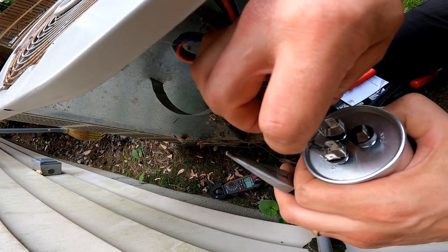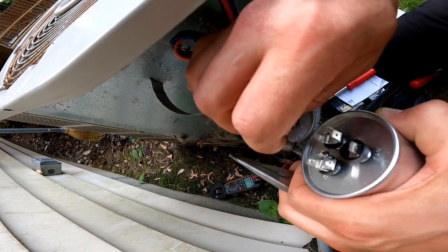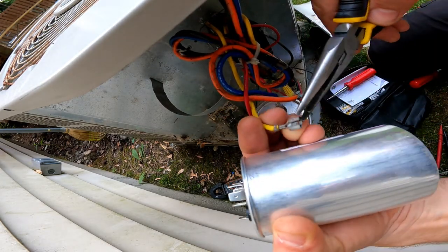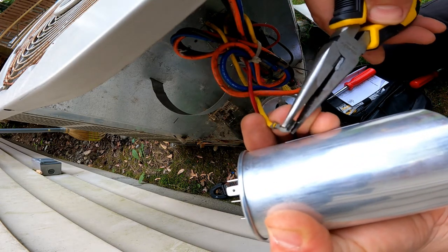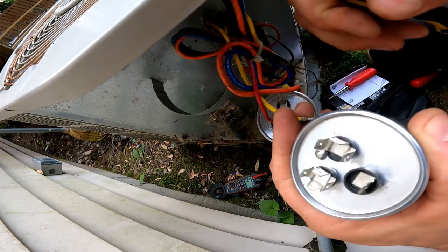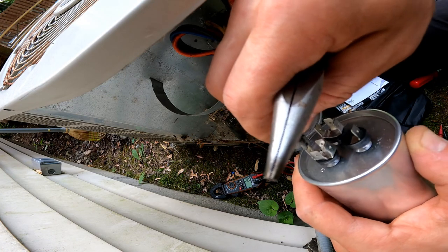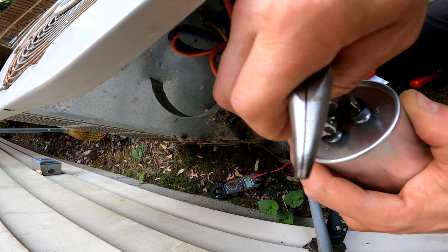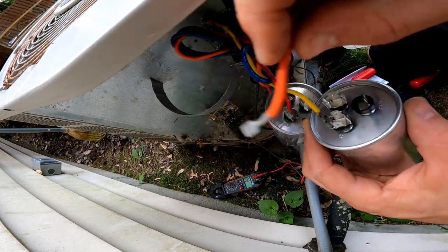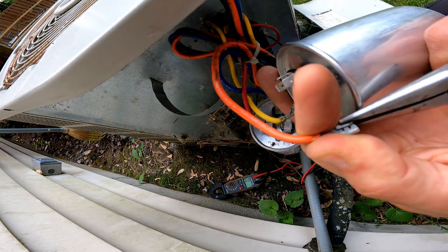Well, one of the things that I've found sometimes is that when those get loose, they're just real sloppy, like they're on and off real easy. What you do is you take your pliers and you just smash them down just a little bit, all right? And that's gonna allow for your contact to be better, it's gonna hold everything nice and tight. I'm gonna notice there's gonna be some resistance now as I shove those on, and they're gonna be on there way better. So let's go ahead and put those on common. I'm gonna just smoosh those down a little bit.